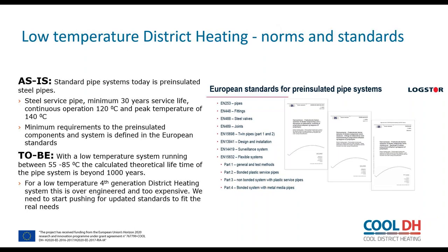Generally speaking, today's standard pipes are steel pipes heavily regulated by European standards, calculating a minimum service life of 30 years, maximum continuous operation at 120 degrees and peak temperature at 140. When we look into a low temperature system, we are talking about much lower temperatures. And if we calculate the theoretical lifetime of a system based on the same standards, we run into a system that is designed to last for more than 1,000 years.